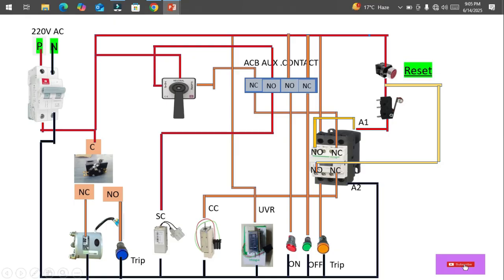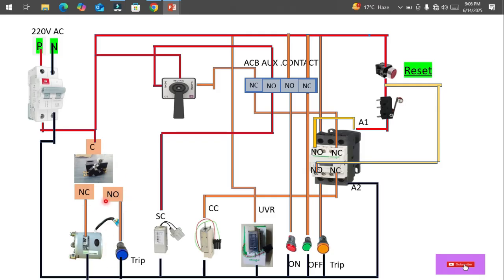First let's discuss the components. This is the auxiliary power supply of the control wiring of the ACB — it's a 220-volt supply source. Next is a limit switch, or micro switch, for the spring charge motor. That detects the maximum limit or tension of the spring charge. This is the spring charge micro limit switch, and this is the universal motor for the spring charge. This indicator will glow when the spring is charged.